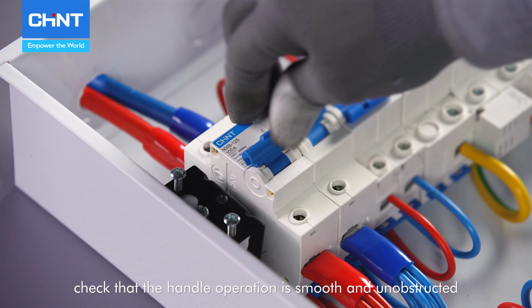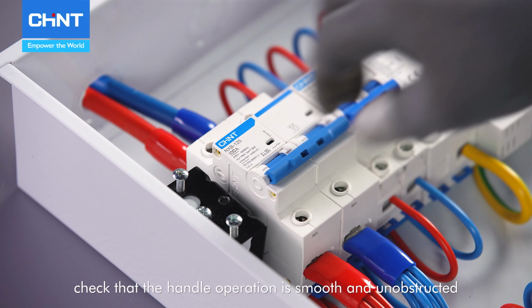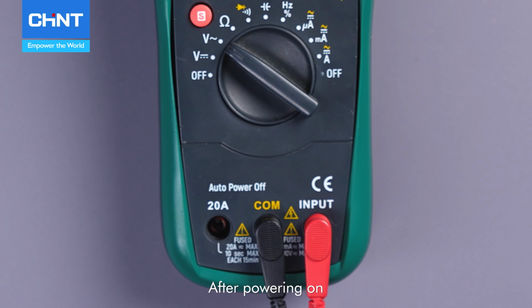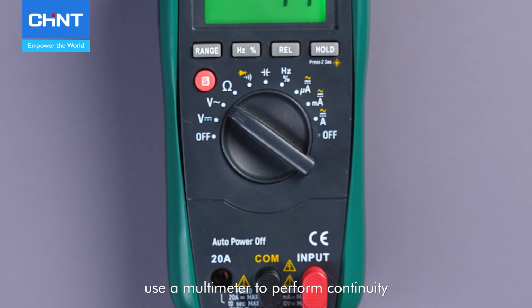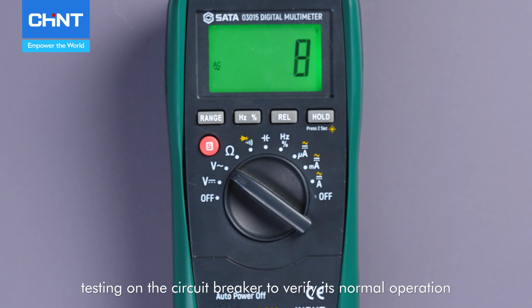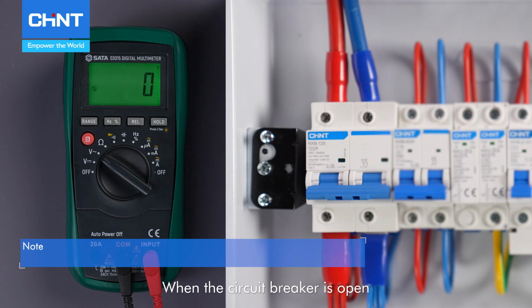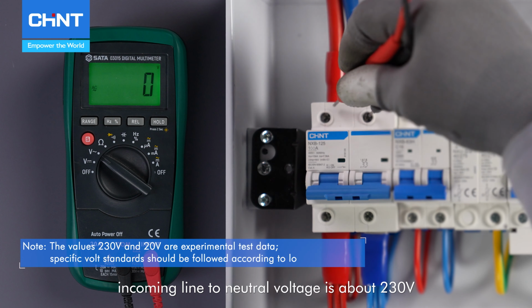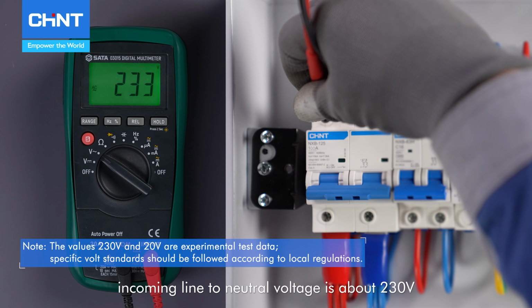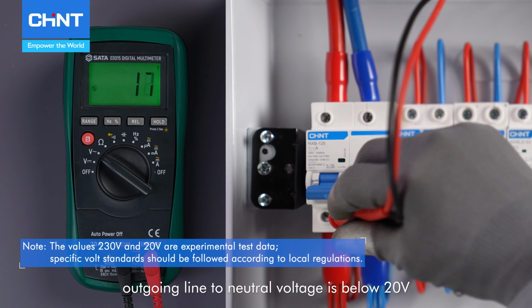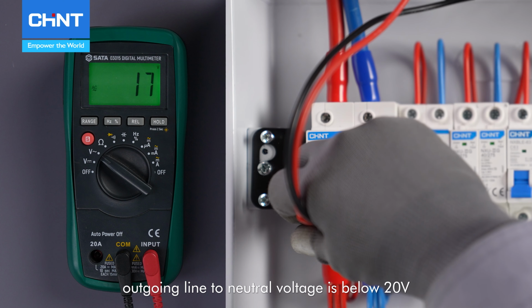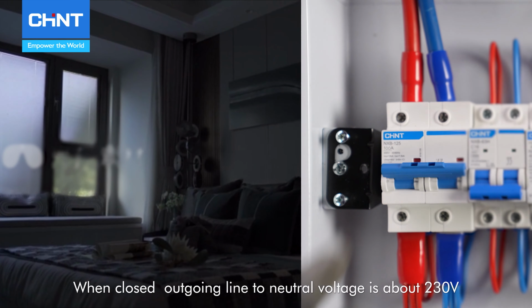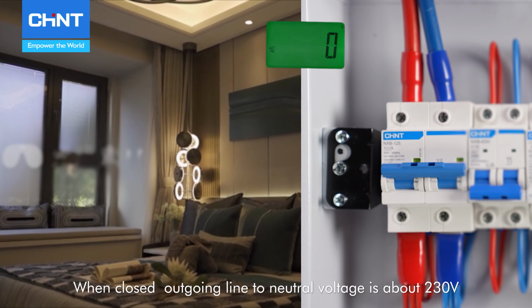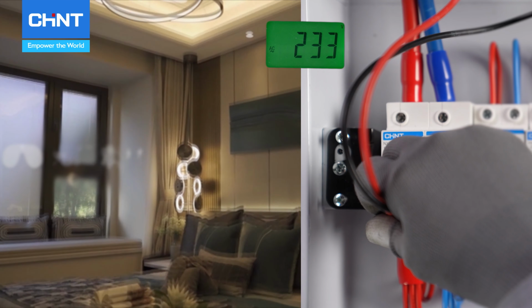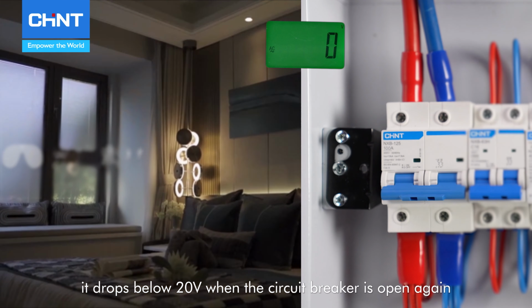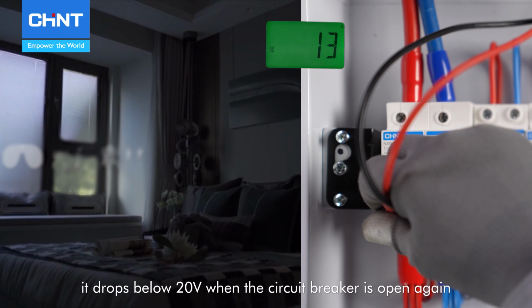Before powering up, check that the handle operation is smooth and unobstructed. After powering on, use a multimeter to perform continuity testing on the circuit breaker to verify its normal operation. When the circuit breaker is open, incoming line to neutral voltage is about 230 volts. Outgoing line to neutral voltage is below 20 volts. When closed, outgoing line to neutral voltage is about 230 volts. It drops below 20 volts when the circuit breaker is open again.